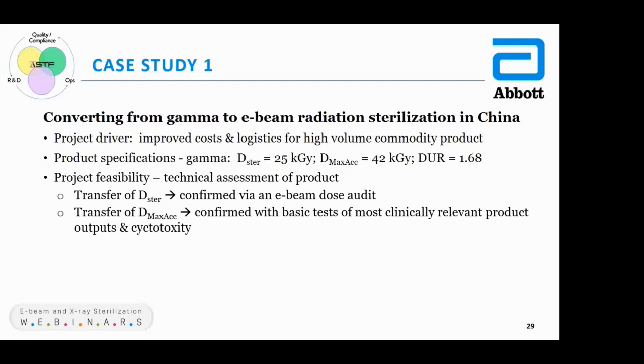So it's appropriate to transfer that dose from the gamma facility to the e-beam facility. Then we look at max acceptable dose - can we transfer that, i.e. is the product compatible with e-beam as it was with gamma?